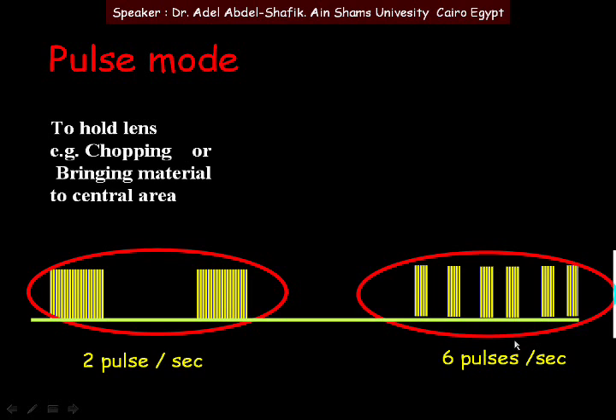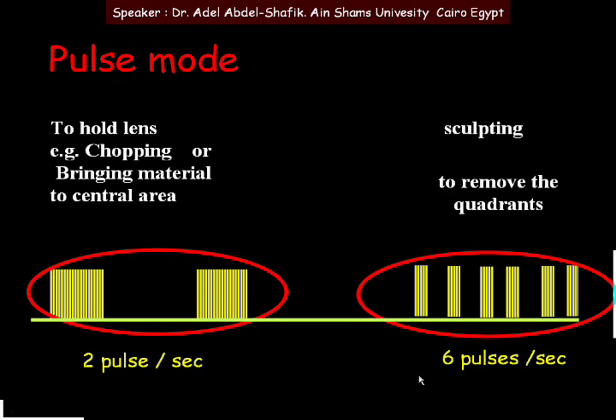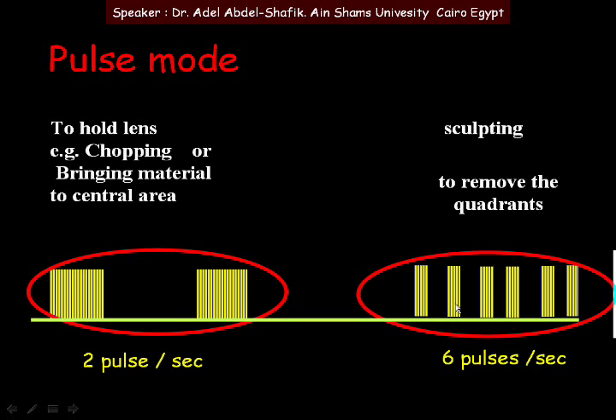Adjusting to six pulses per second gives shorter off periods and is used for removing lens material — such as scrape and sculpting or removing quadrants. The ultrasound takes material, then a short off, then more ultrasound. Long off means better holding; short off is suited for material removal.